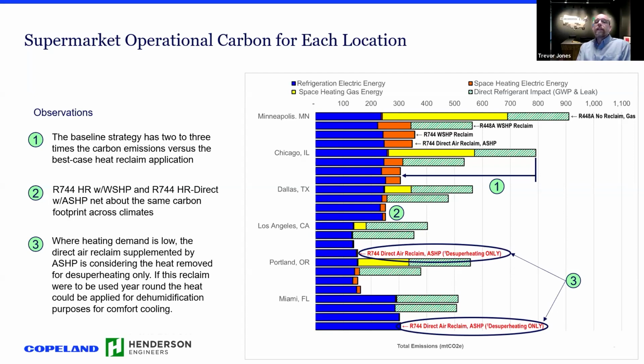When we look at Los Angeles and Miami, where we have very low heating, we looked at just desuperheating only. This is probably going to be a more common strategy in those very warm climates, to not fully condense your refrigerant. It does allow for a simpler system on the air side if this is used. It's not quite as good as the water source heat pump, so slightly more energy, but it is a much simpler system. Desuperheating would also lend itself to something like dehumidification reheat for comfort cooling. We didn't include that as part of the study, but it is a possible use case.